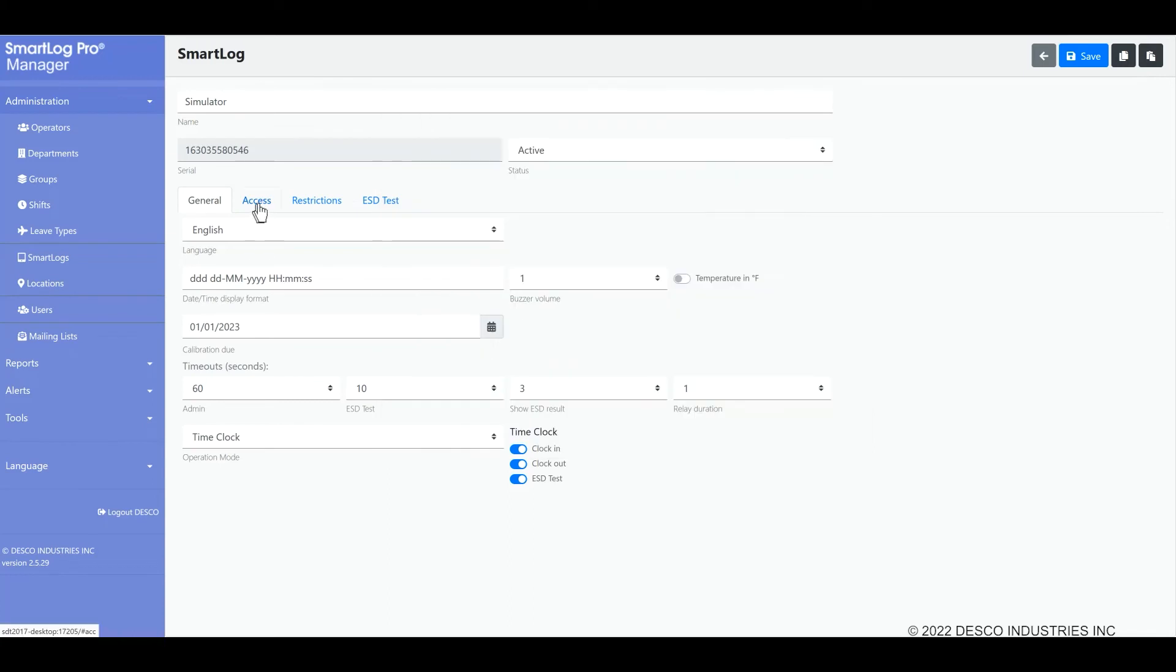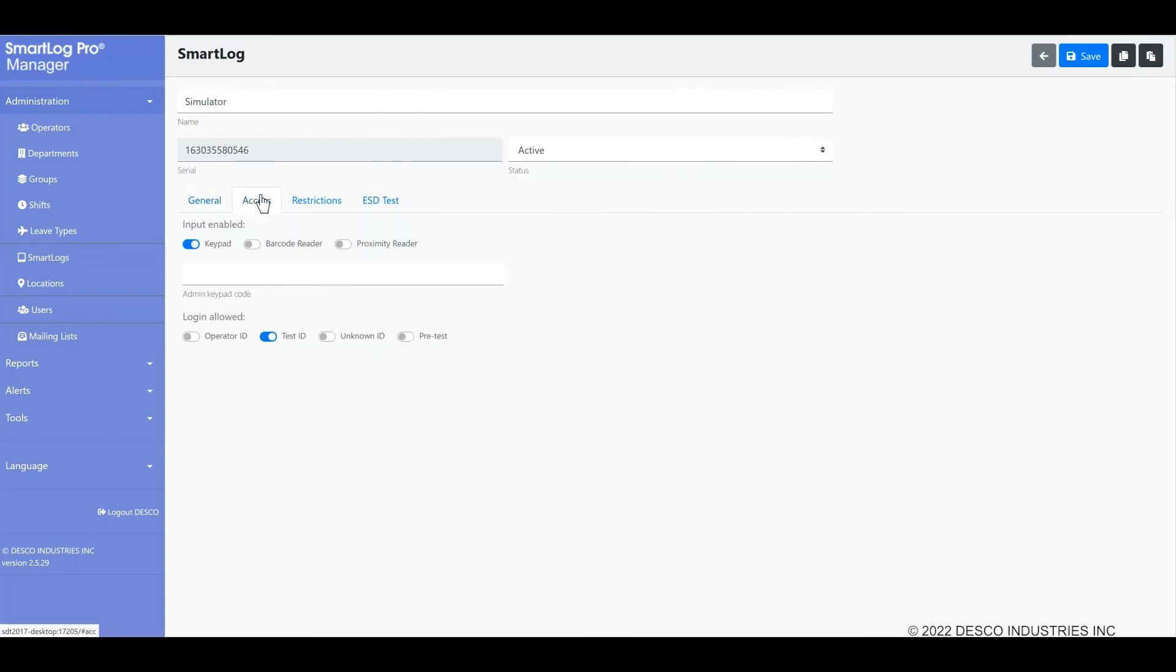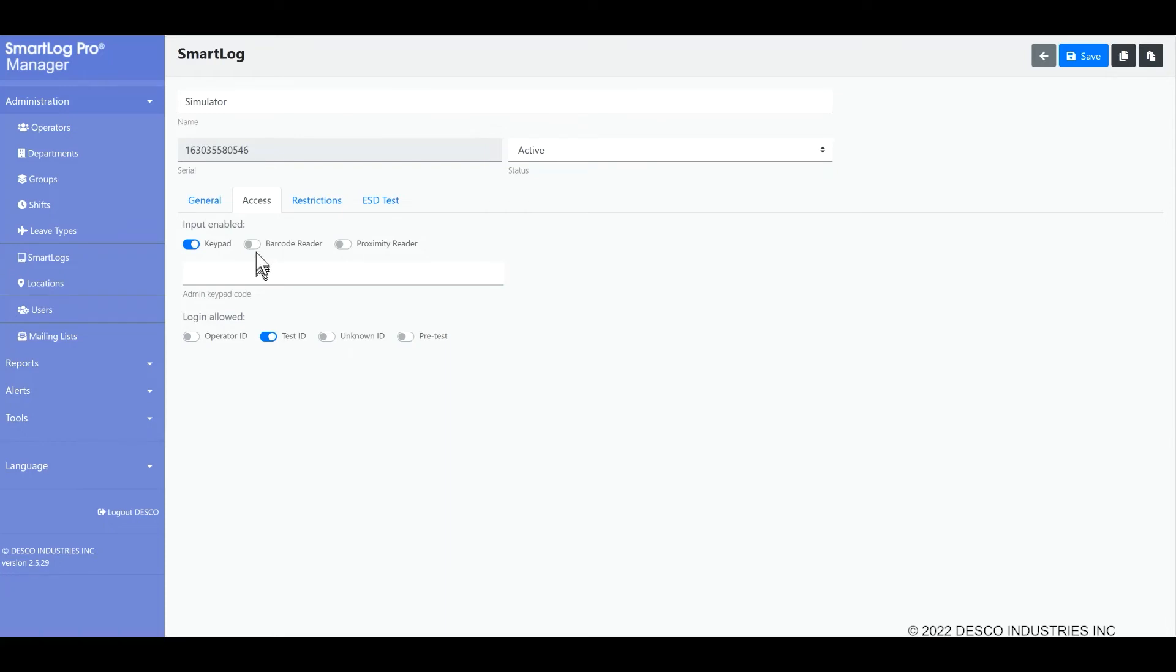The access tab defines available access methods and login options. This is where you may specify which readers are in use on the SmartLog Pro SE. If you do not use the barcode reader, for example, because you only use proximity badges, you may disable that option. You may enable the keypad option, so if an operator loses or forgets their badge, they may type their number in on the keypad as an alternative way to log in.